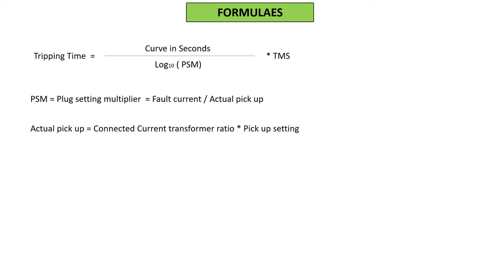To find pickup value, we multiply current transformer connected ratio by relay pickup setting, which is in percentage. There's a difference between current transformer and current transformer connected ratio. The CT can be 800/5 or 400/5, but what we set in the station is the connected CTR - that could be 400 or 800. Please note this carefully.